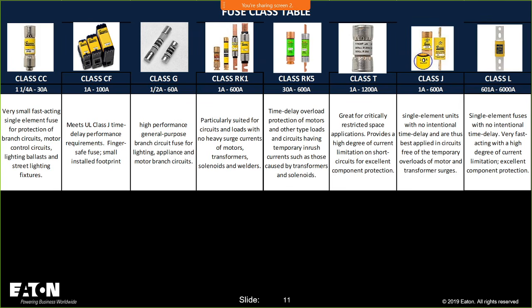These are what you see on those little transformers that you'll have in industrial power systems, where you have a little control power transformer type of deal. These CC fuses, you'll see that there. They only go up to 30 amps. So you'll notice, again, you'll have an overlap. This goes up to 30 amps. Obviously, I can get a Class CF in 30 amps. I can get a Class G in 30 amps. I can obviously get an RK1 in 30 amps on RK. So I can get 30 amps in any one of these fuses.